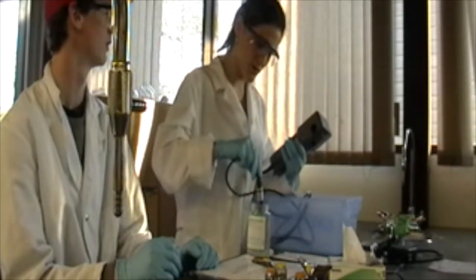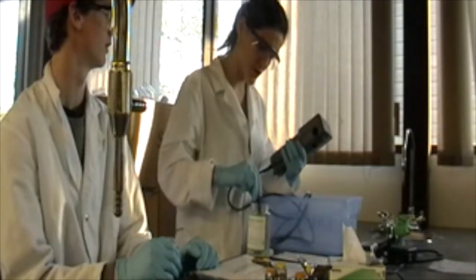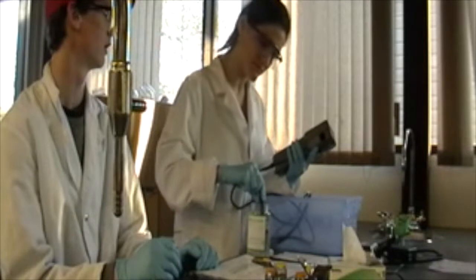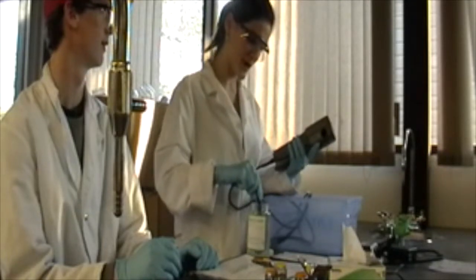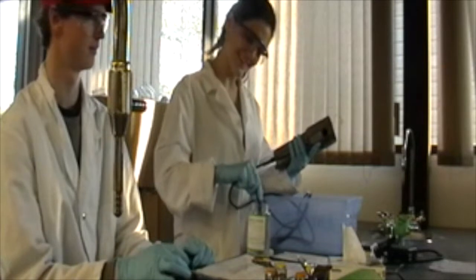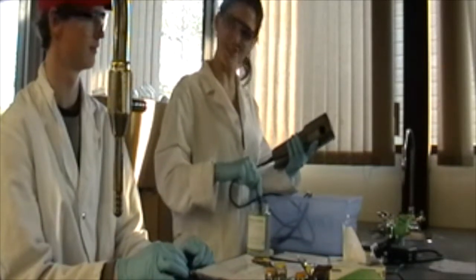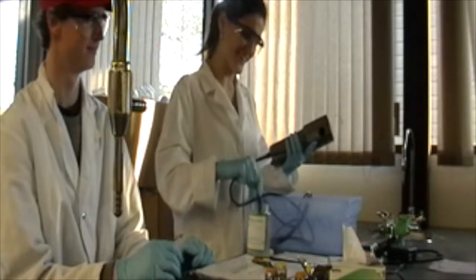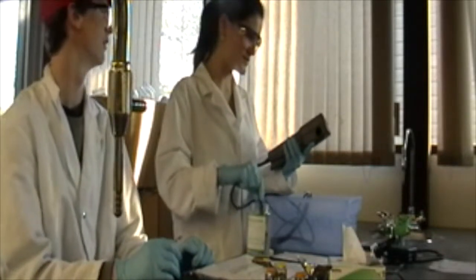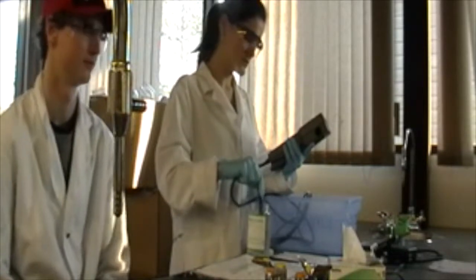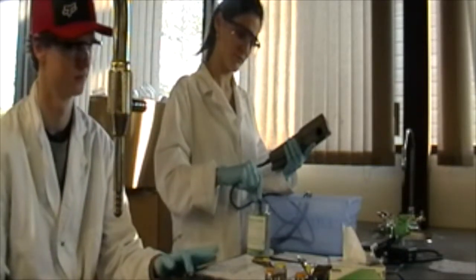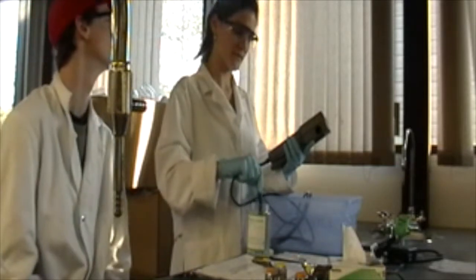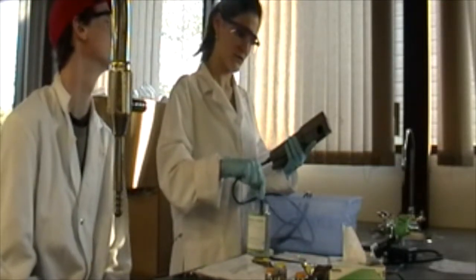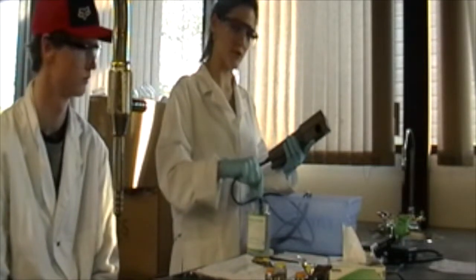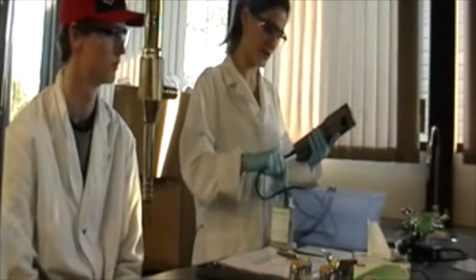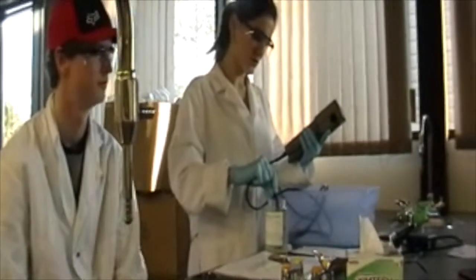So now we insert the probe into our sample, and we have to submerge it all the way up to the cable or deeper at all times. So we're going to be bobbing the meter up and down, trying not to hit the bottom, like we're jigging for fish. So, gotta be a little patient here. We gotta wait for the readings to stabilize. So that's gonna take some time. So we always have to make sure that the probe is completely submerged during the testing. Otherwise, you're not gonna get the proper reading.